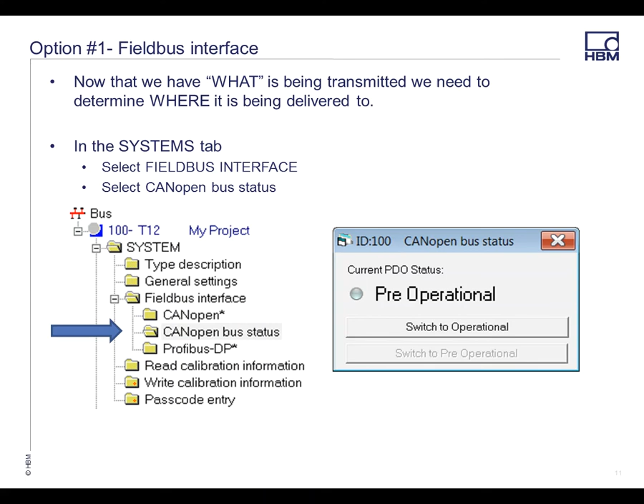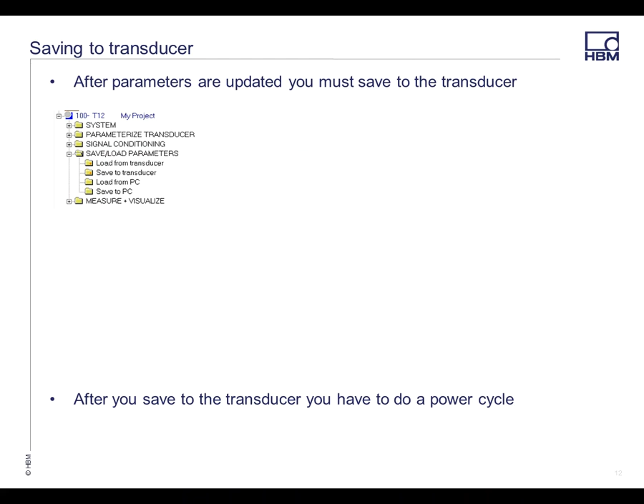The next thing you want to do is save to the transducer itself. On your T12 Assistant, one of the options is save load parameters. There are 4 different parameter sets you can use. Anytime you make a change to the actual transducer, save it to the parameter sets. This way, if the power goes out on your rig, once it comes back on it should respond and come right back to that same setting, so you shouldn't have to do this again.